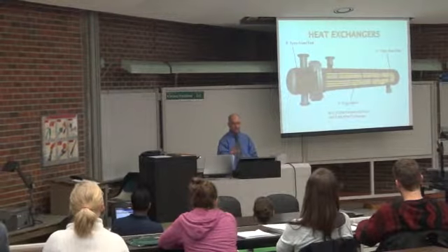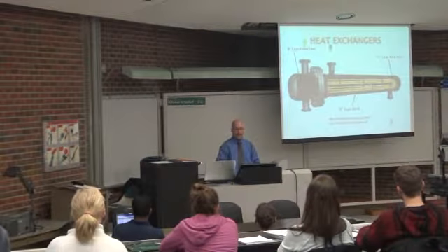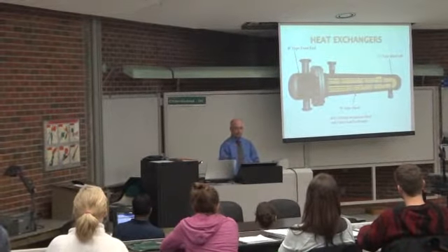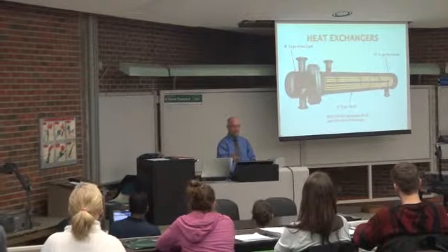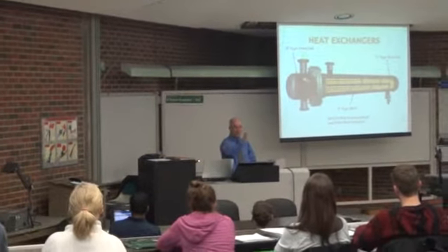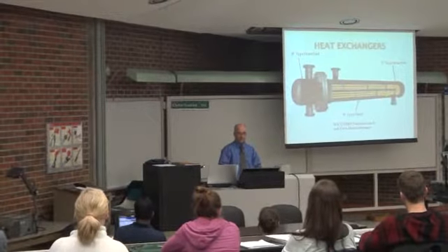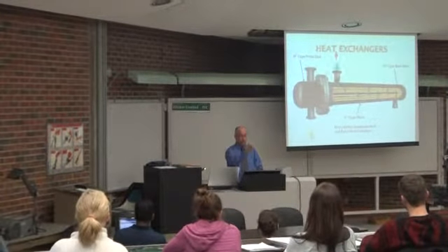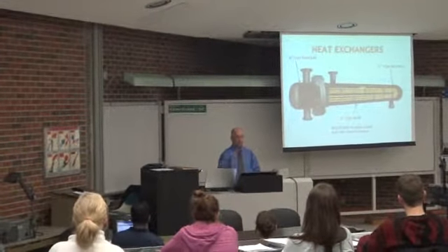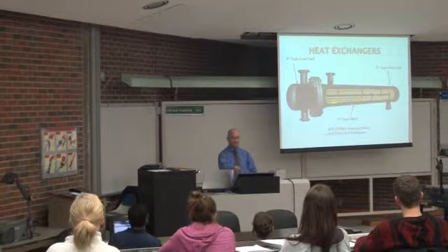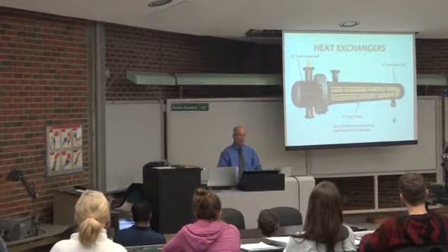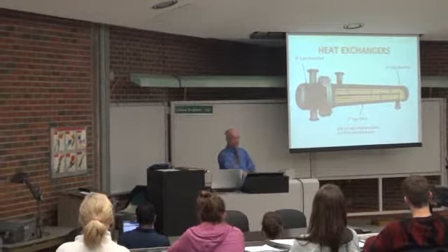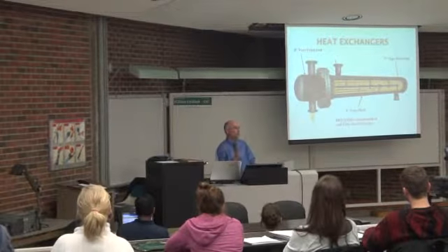So that's an E-type shell, which means it's a single-pass shell, and a U-type rear end. So the fluid on the shell side, how it comes in through the top nozzle on the shell. That's the red fluid. It's a cross-flow exchanger. It moves itself around the segmental baffles and exits in the shell nozzle at the bottom. So most of the heat transfer will occur in this exchanger across the tubes.